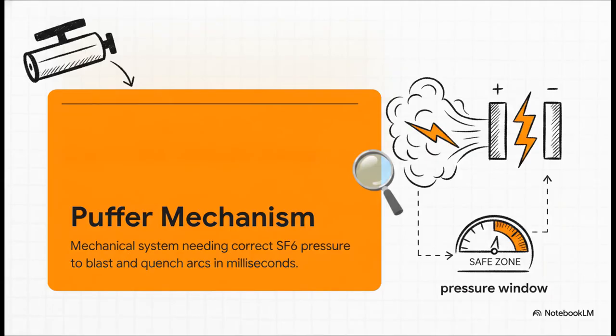So, remember the puffer mechanism? We talked about how it acts like a high-speed bicycle pump, blasting ionized SF6 gas to snuff out an electrical arc in literal milliseconds. But here is the catch, and this is what we really need to master today. That mechanism only works safely inside a very narrow, highly specific pressure window.